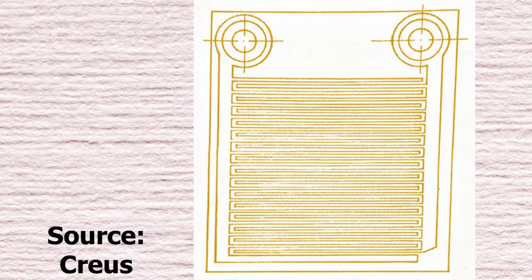The relative humidity measurement lithium chloride cell consists of a lithium chloride embedded cell with a gold foil grid. Salt has the property of varying considerably in resistance with increasing or decreasing ambient humidity, since it releases and absorbs ions from the support film. Since the relative humidity is determined simultaneously by the moisture content and the air temperature, it is necessary to compensate.